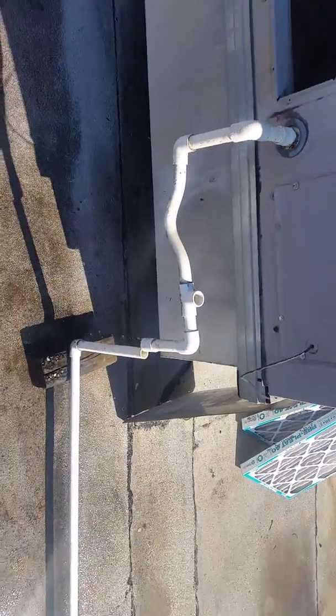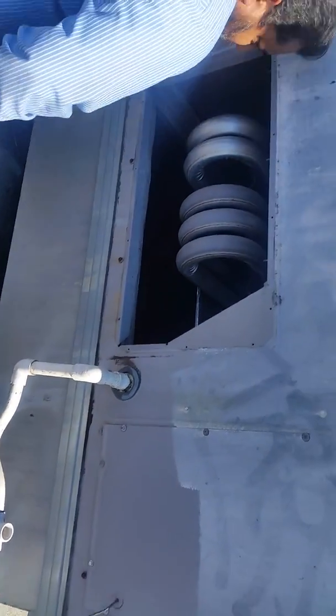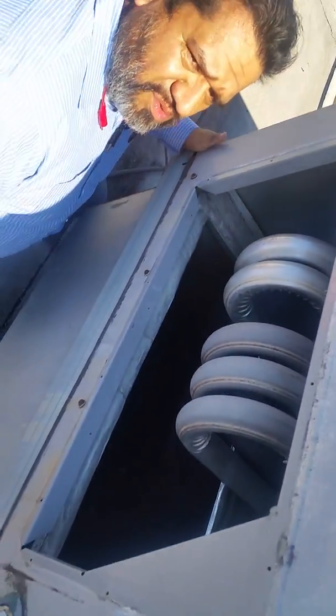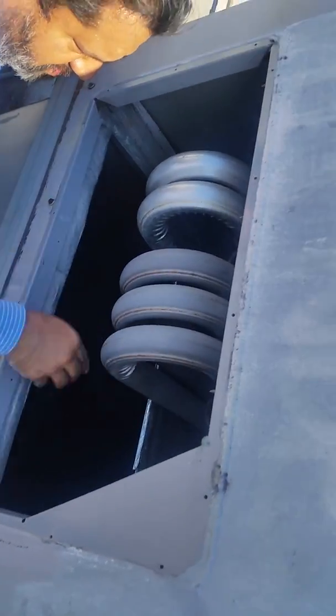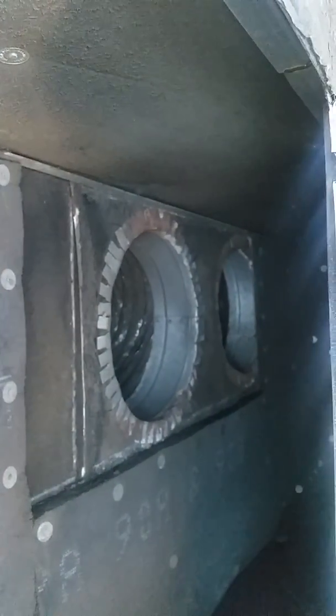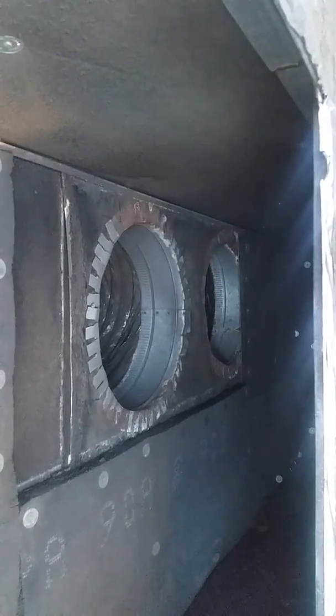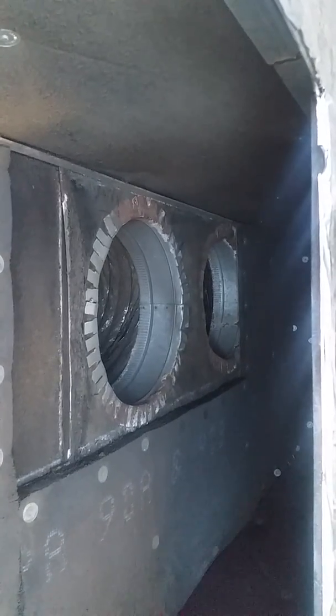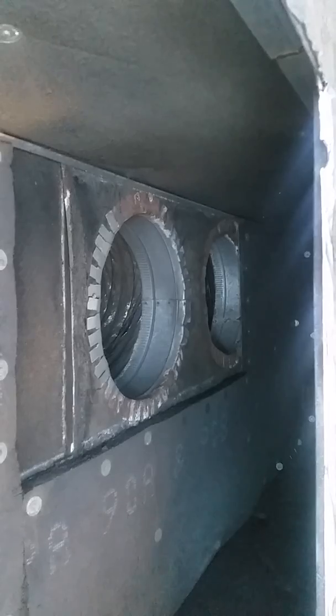Here's the drain line, so you can see. On this unit, the heating operation was turned off. Looking at the heat exchanger, let me point it out right here. I see some questionable area. The heat exchanger right here has some rust that may be leaking by there. Another thing that I saw is that this unit has 2 14-inch supply ducts. I don't think that's enough, but I'm going to be checking the ductwork here in a minute. Some more detail on the ductwork, but that's only the 2 14-inch supply ducts.